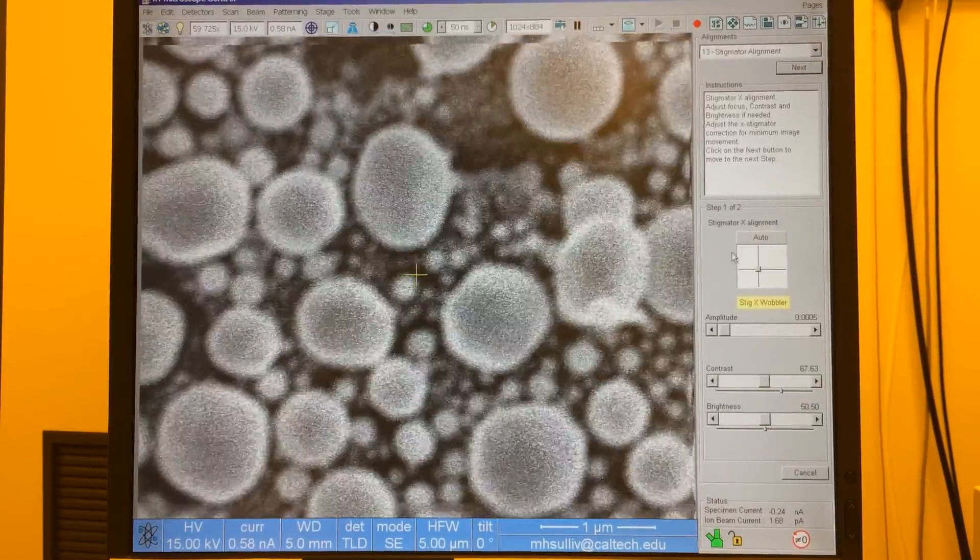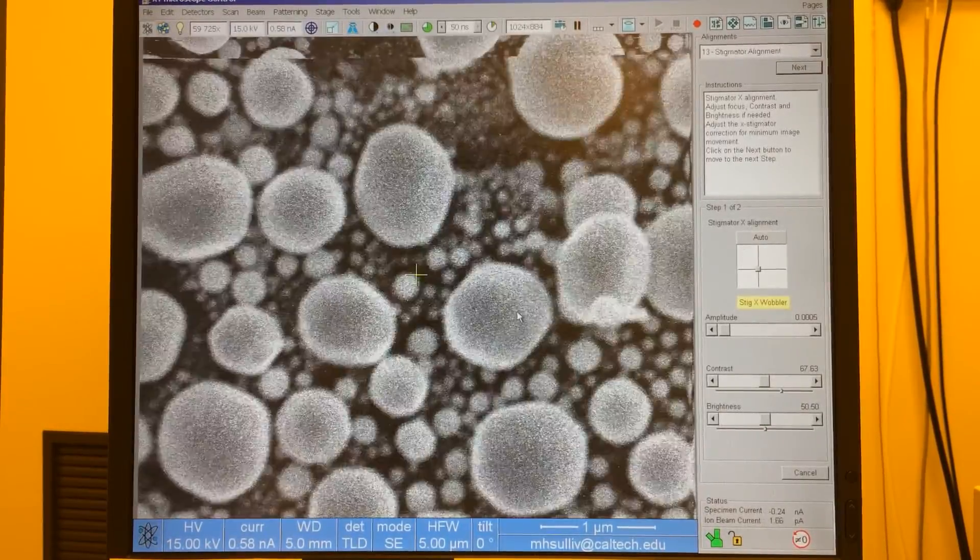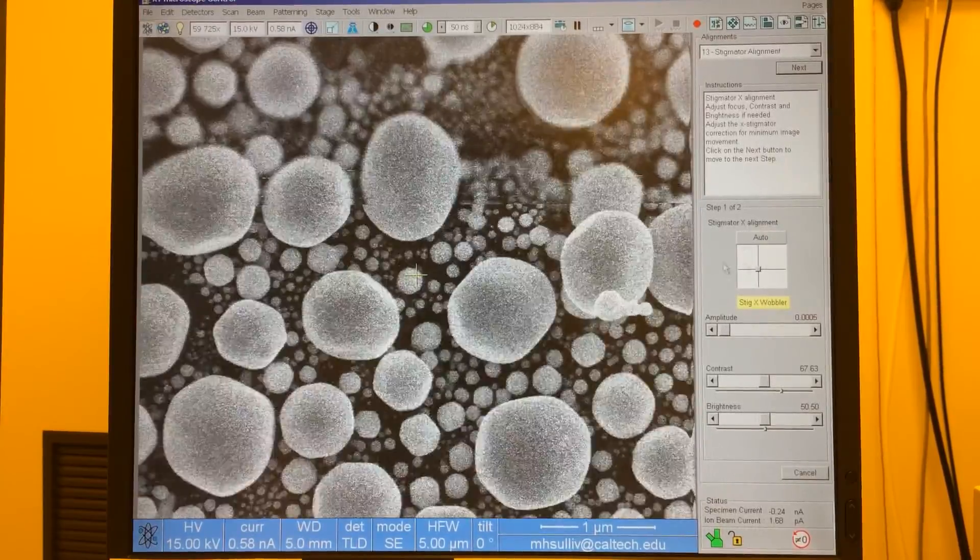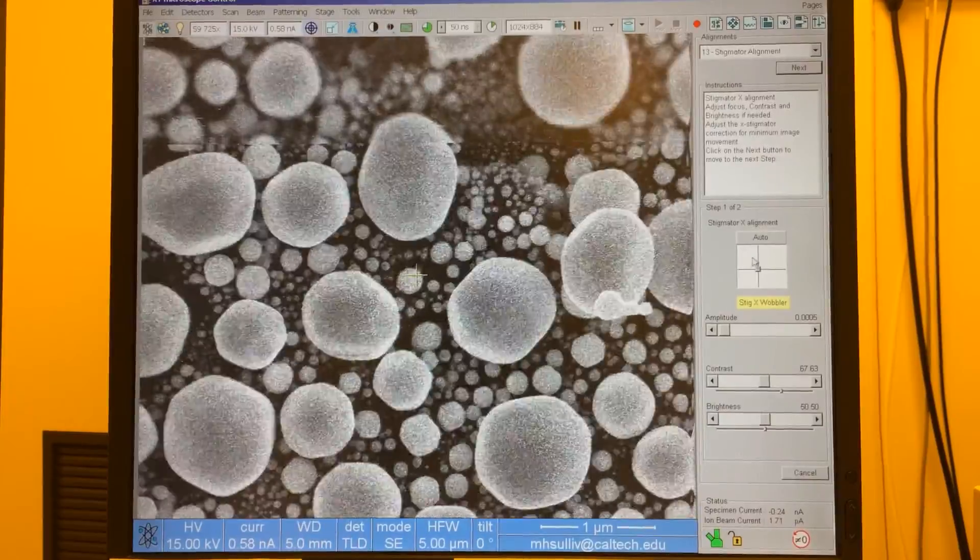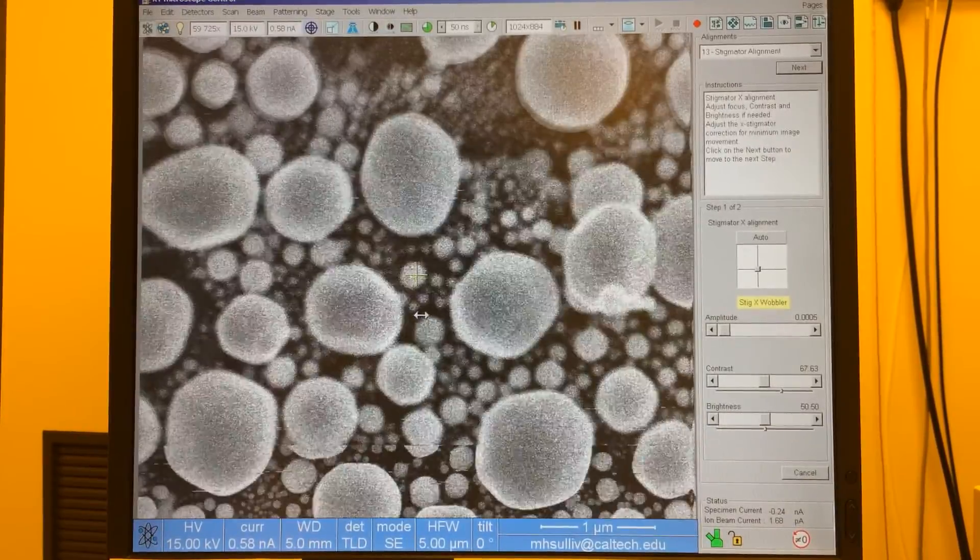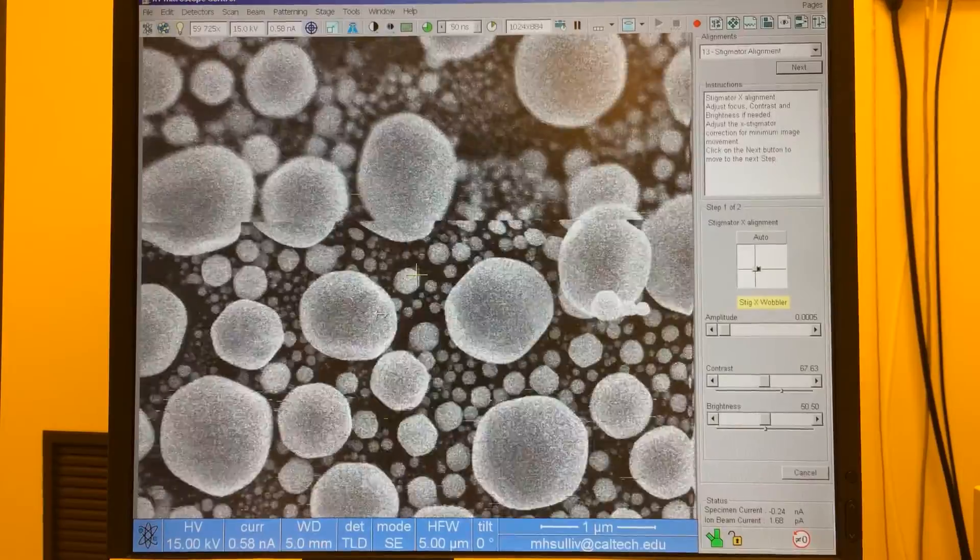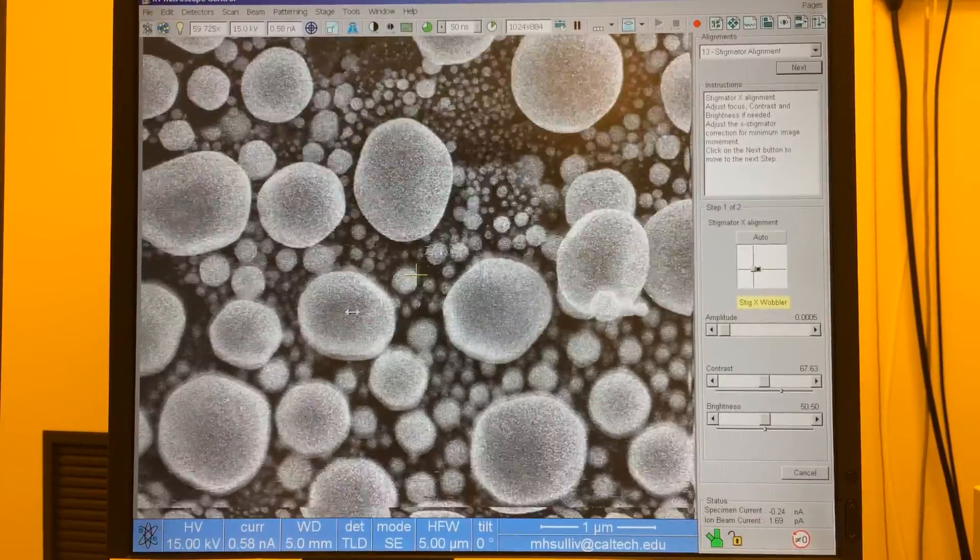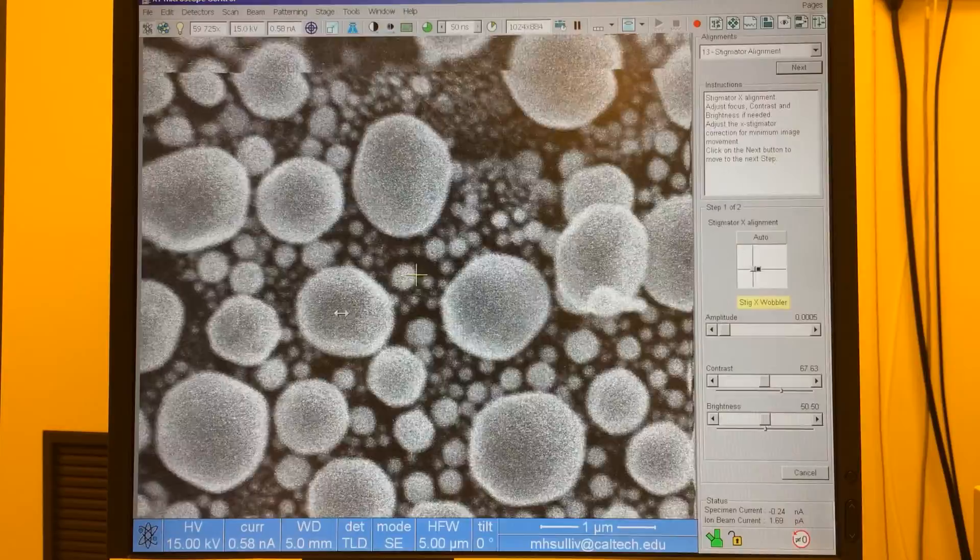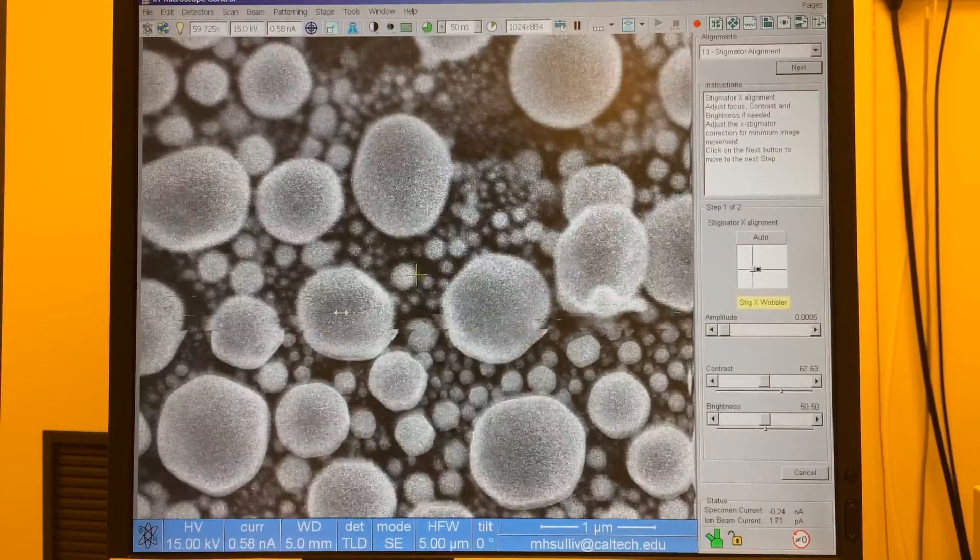Now to fix this it's the same way we fix lens alignment. If I see it's moving on a diagonal I want to fix the x and y oscillation independently. So to fix x I'll grab the vertical bar and move it left or right. In this case I'm moving it to the left and I can get the particle. Now I've minimized the x oscillation, it's only moving up and down.